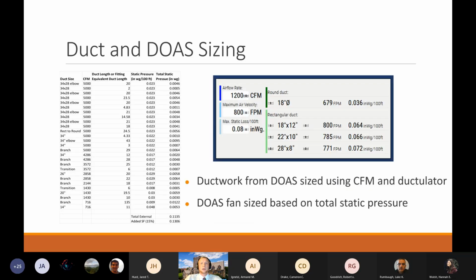Finally, we had to size the ductwork and the DOAS fan. We sized the ductwork using a helpful online duct calculator. All you had to do was input the static loss and enter the airflow in CFM for each branch. And the calculator then provided the appropriate size for both round and square ducts. In order to supply the correct amount of airflow to the farthest point in the duct line, the DOAS fan was sized properly so that it could overcome the static pressure.